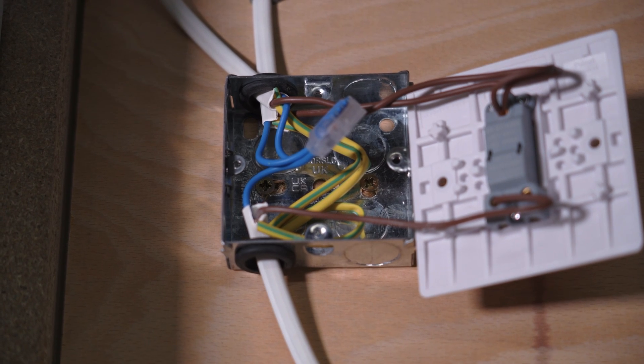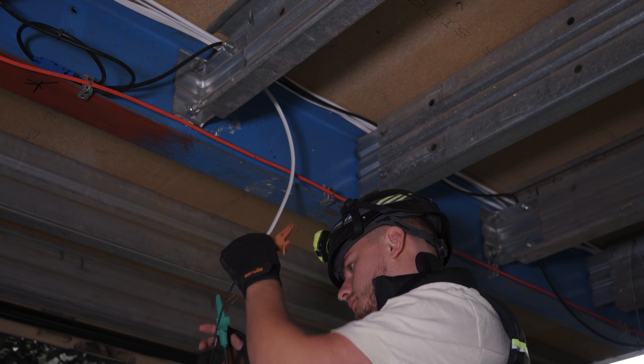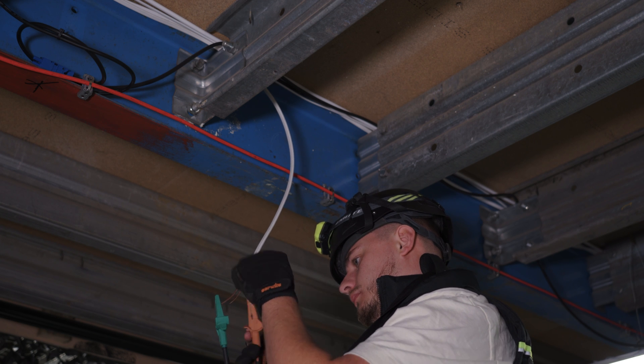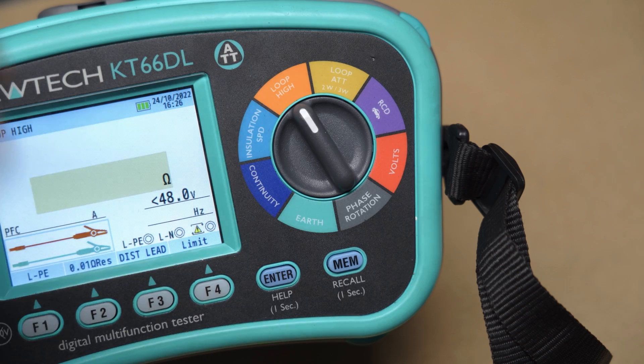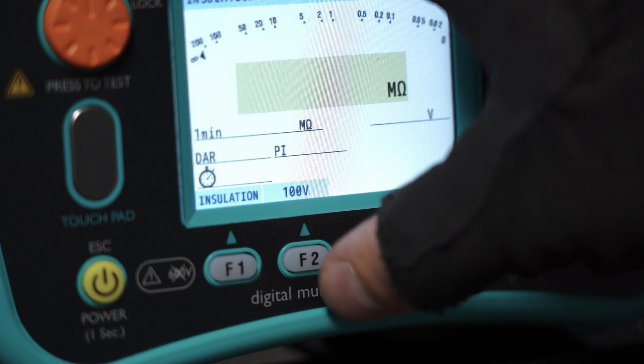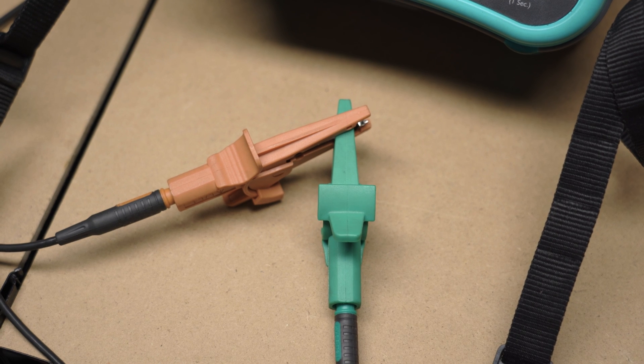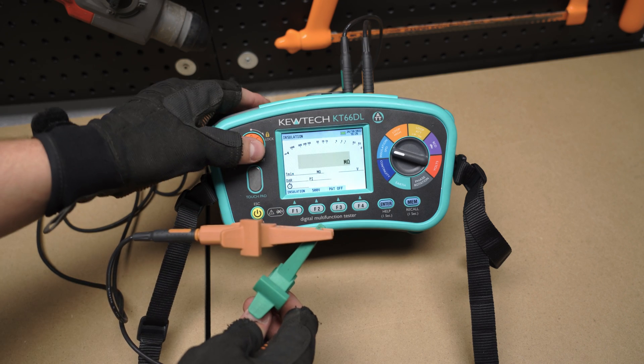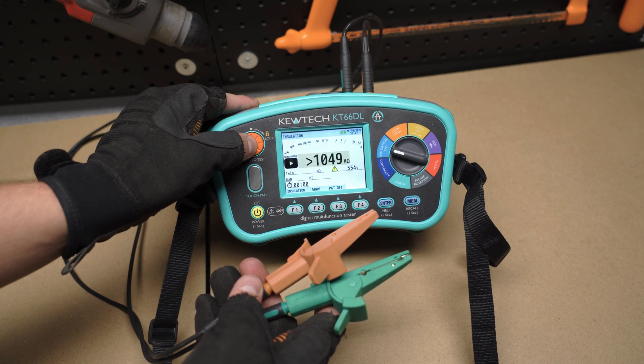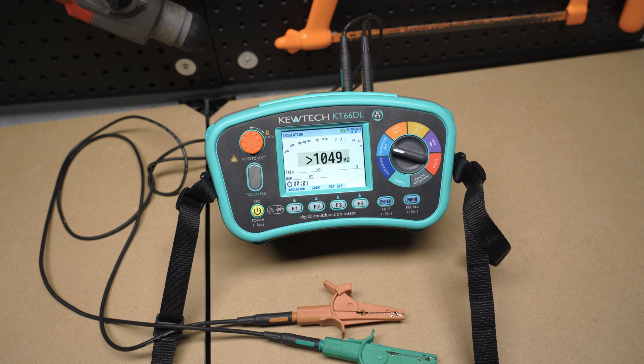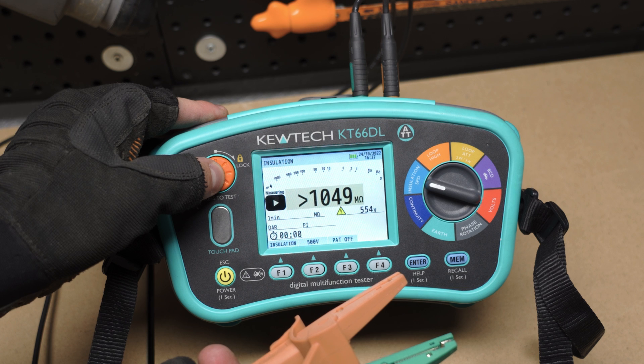For this explanation we'll assume the circuit has a nominal voltage of 250 V, it's been tested during the construction phase at 500 V, and now we're doing initial verification. Get your MFT or insulation resistance tester out, set it to insulation resistance mode, and set the test voltage to 250 V. Before getting stuck in, connect your leads together and press test — a dead short of 0.00 should appear. Then take them apart and press test again — the resistance should be greater than the range of the tester. This confirms your leads are good and shows you the range and limitations of that test voltage.